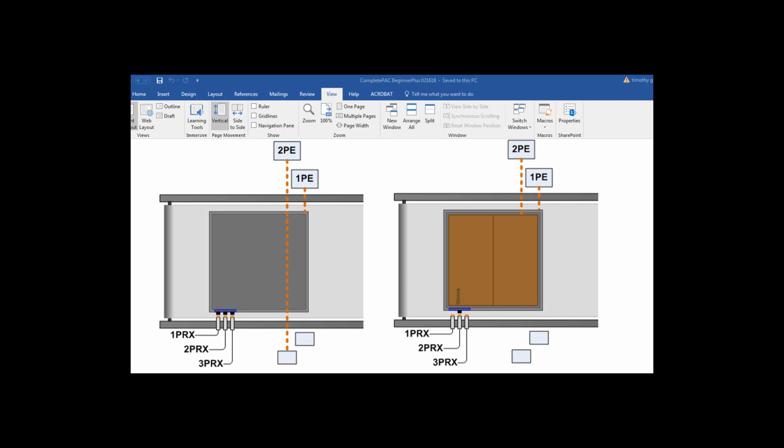In the second diagram, you can see that there is only 1 bolt head, so when it hits the photo eye, if your logic reads the state of those 3 proximity switches, it is basically encoding a value of 0 through 7. 3 bits give you 8 possibilities, 0 through 7.